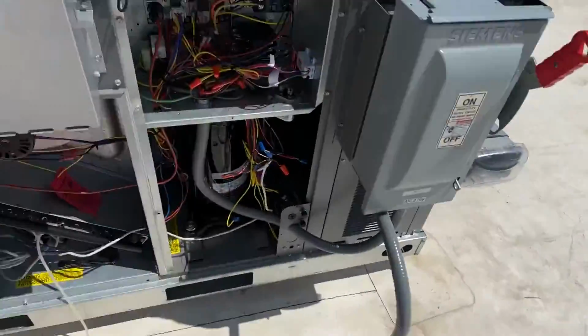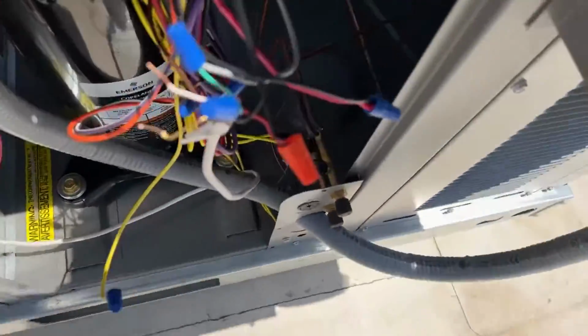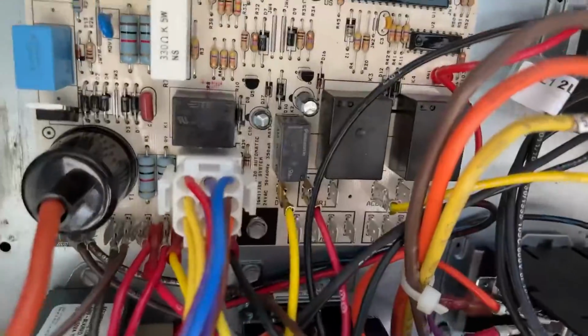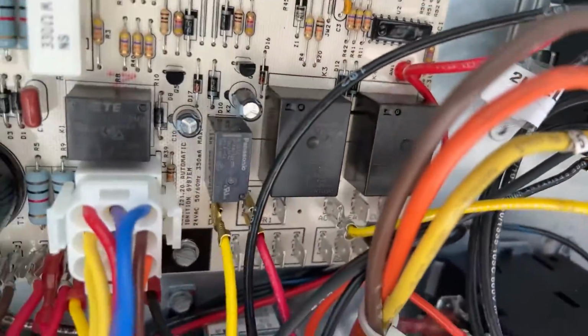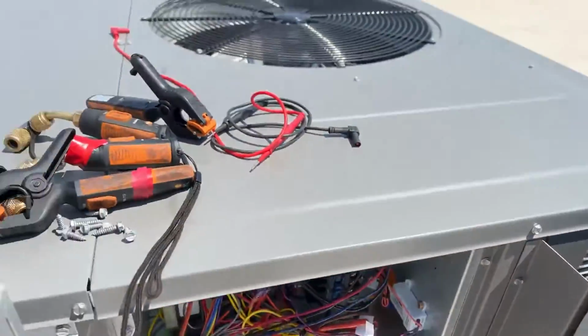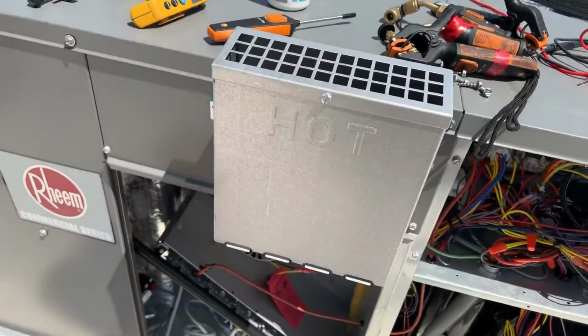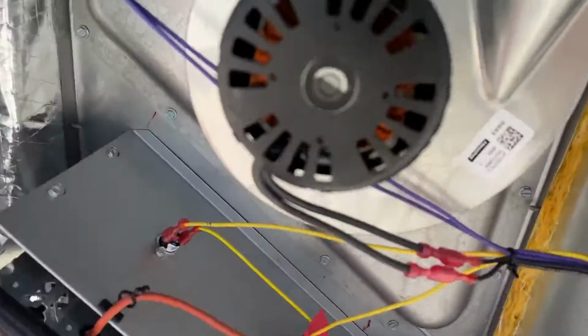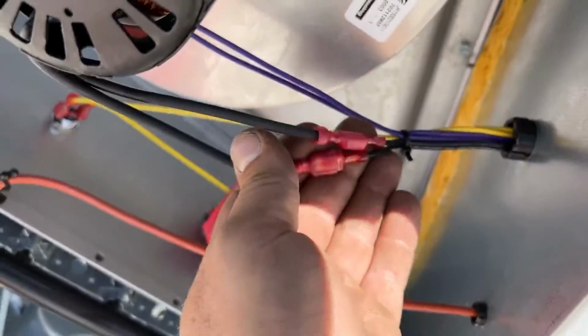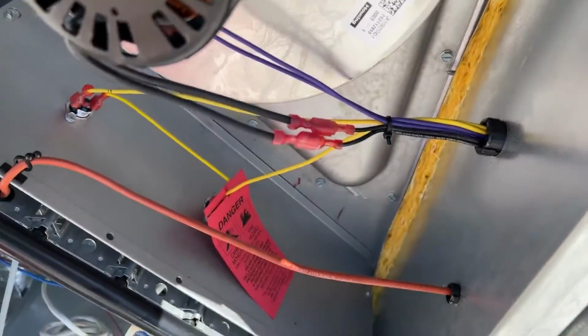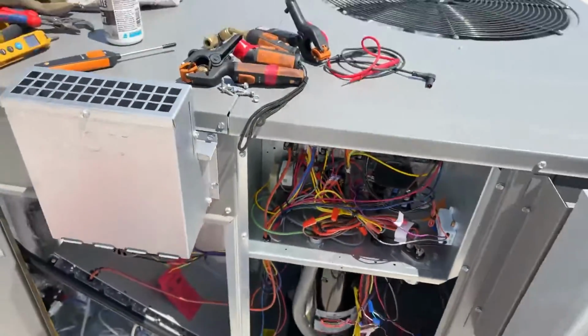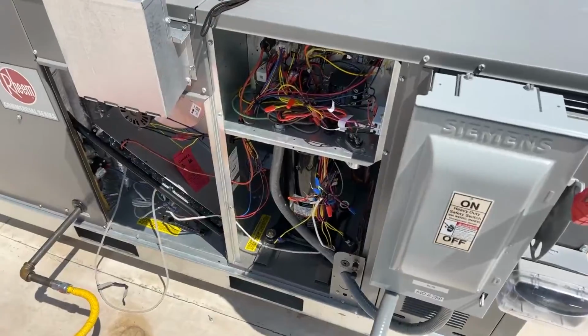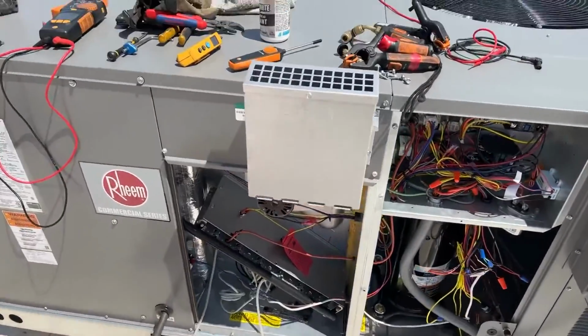1400A. We are engaged for heat. The board says it's trying for heat. Getting a 2-code error, which is inducer motor or pressure switch. No life out of this bad boy. And 50 volts here, so something's not right. Sending voltage to that motor, but moving on.